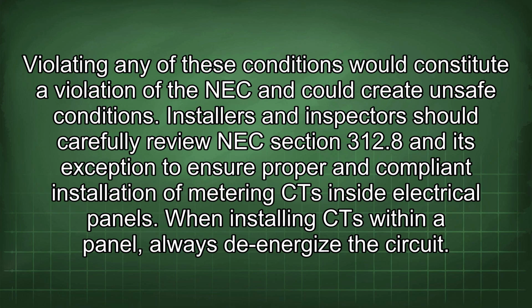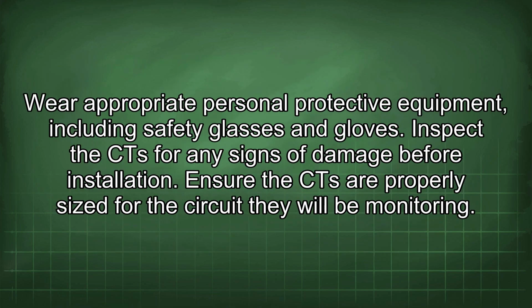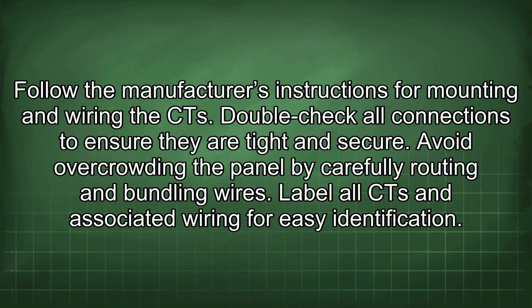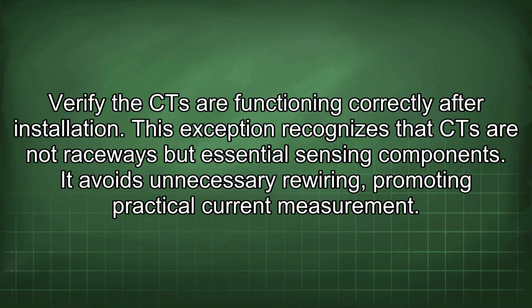CT inside electrical panels. When installing CT within a panel, always de-energize the circuit. Wear appropriate personal protective equipment, including safety glasses and gloves. Inspect the CT for any signs of damage before installation. Ensure the CT are properly sized for the circuit they will be monitoring. Follow the manufacturer's instructions for mounting and wiring the CT. Double-check all connections to ensure they are tight and secure. Avoid overcrowding the panel by carefully routing and bundling wires. Label all CT and associated wiring for easy identification. Verify the CT are functioning correctly after installation.